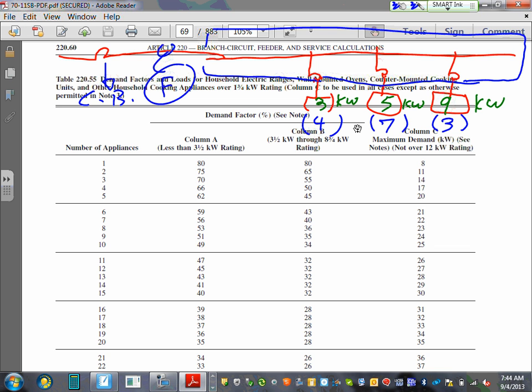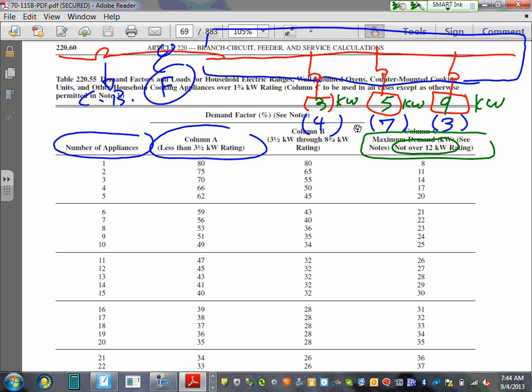Okay. Here's how this table works. Can you guys see the first column says number of appliances. The second column, column A, says less than 3.5 kW. So before I go ahead and start with these guys, first, the default for this table is you take the number of appliances and apply column C to it. That's a default. So look at this. It says maximum demand kW, not over 12. So you can use this table as long as not a single one of them is over 12 kW, right? Not over 12. I want you guys to review all these sizes at the top. Can you tell me if any one of them is over 12 kW?